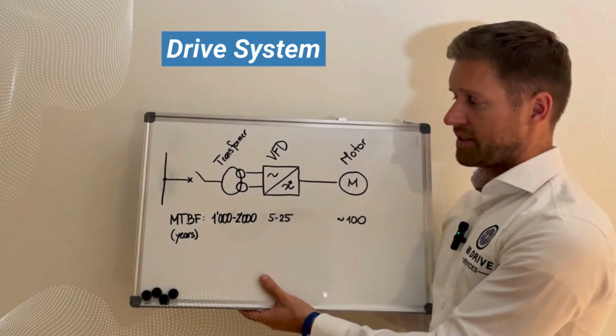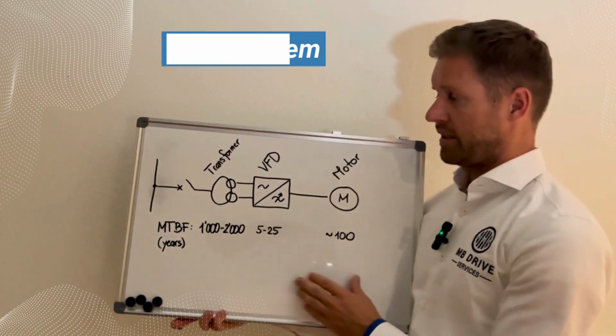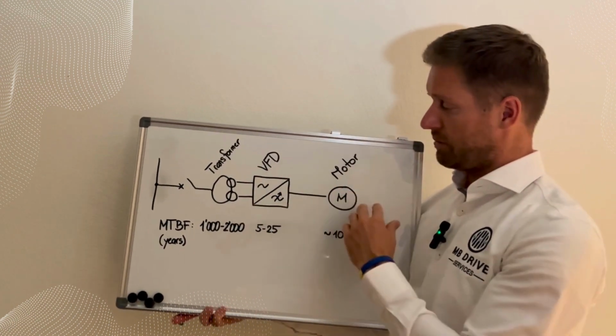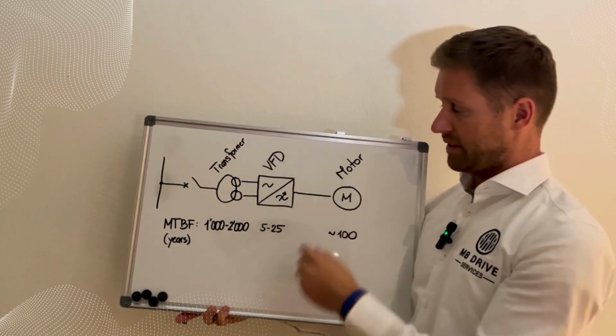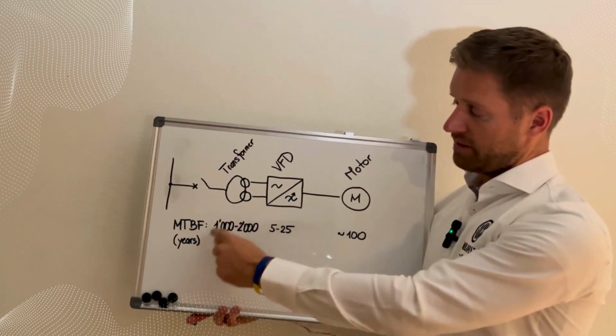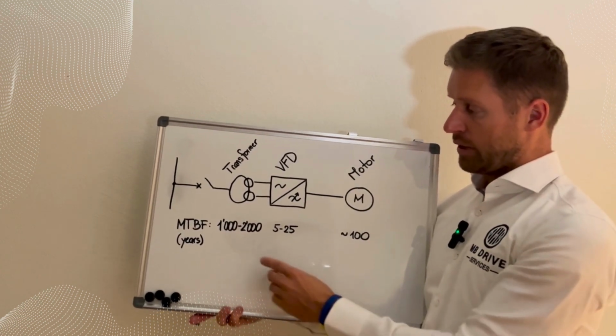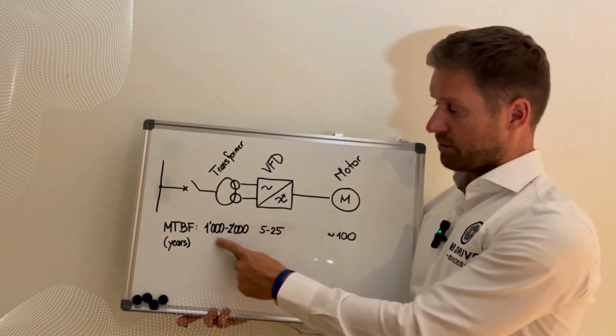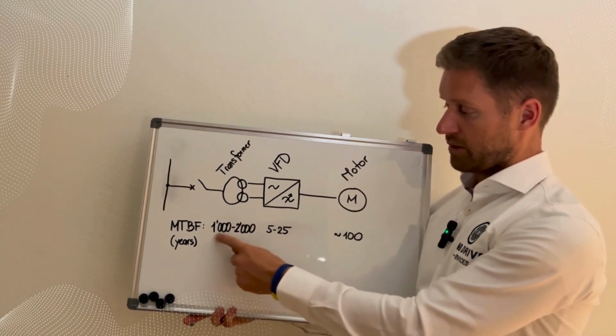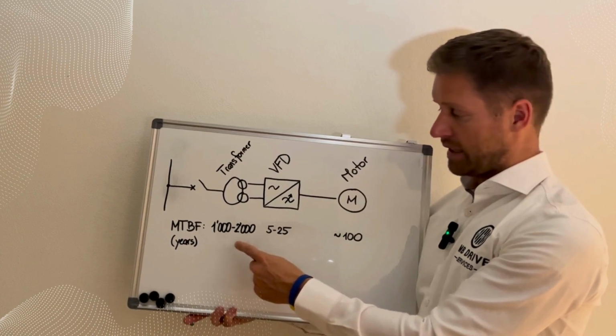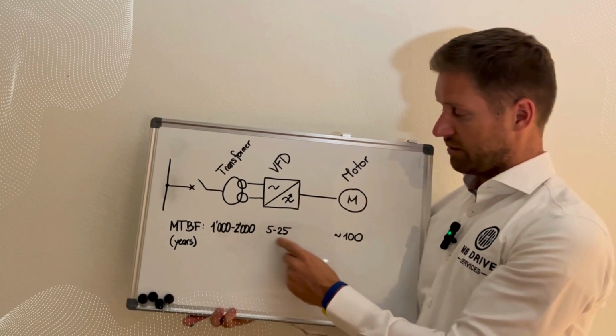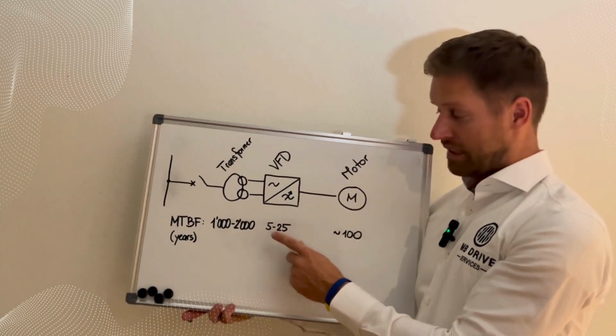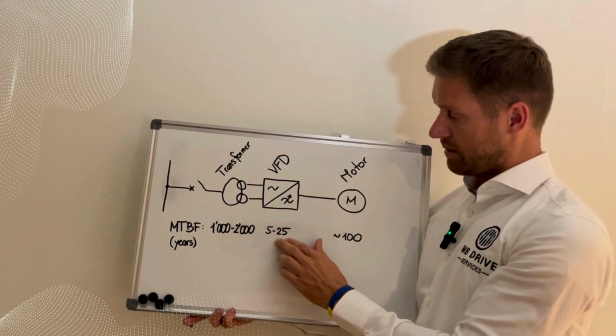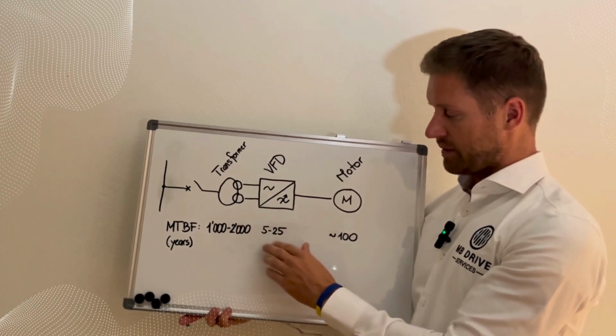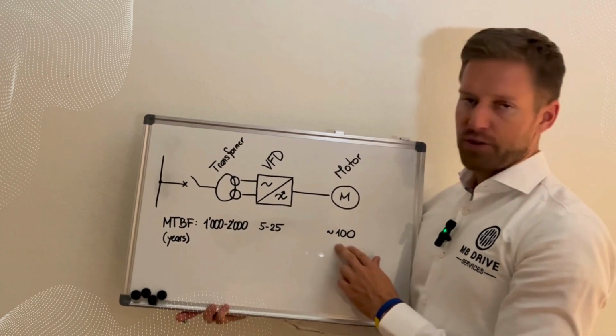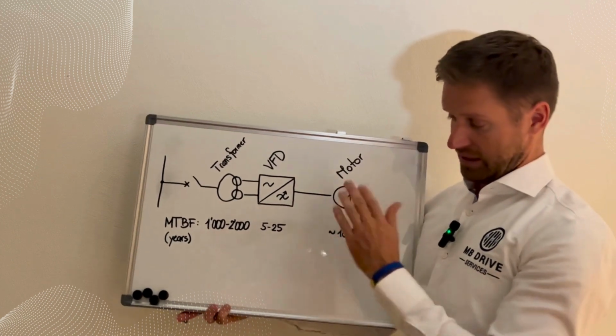Now let's look at the drive system and some specific figures. We will look at three main system components: transformer, VFD, and the motor. And if you look at the MTBF, the mean time between failures: for the transformers, I have seen from different manufacturers figures ranging somewhere between 1000 and 2000 years. For the VFD, you typically get a range somewhere between 5 and 25 years. The 25 is quite optimistic, but let's say 10 to 15 years is quite common. And for the motor, I don't have really good figures, so I just estimate maybe 100 years.